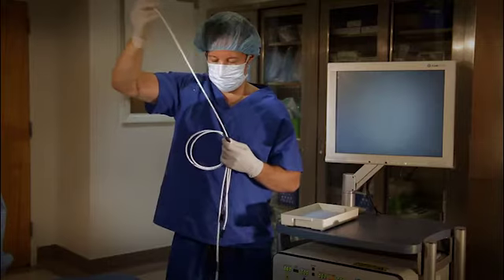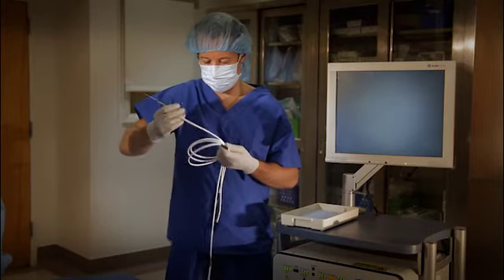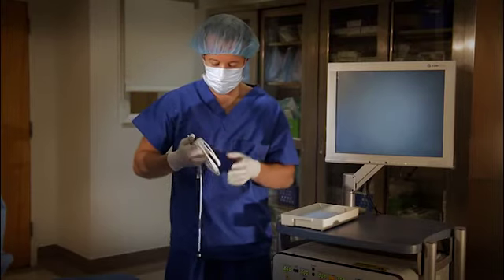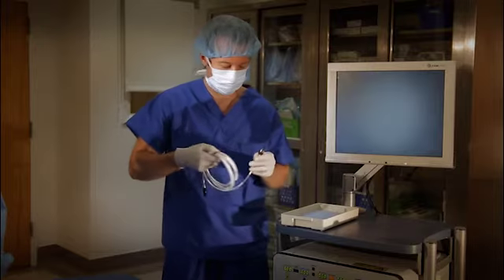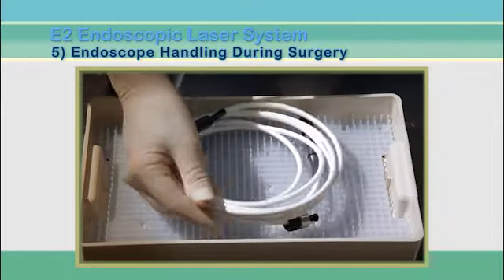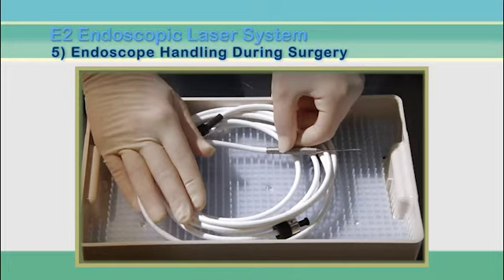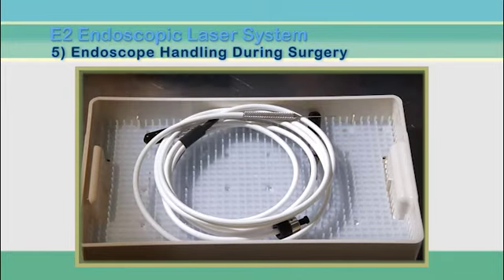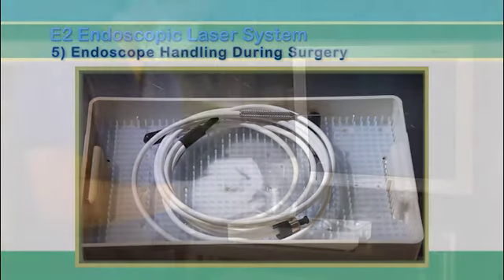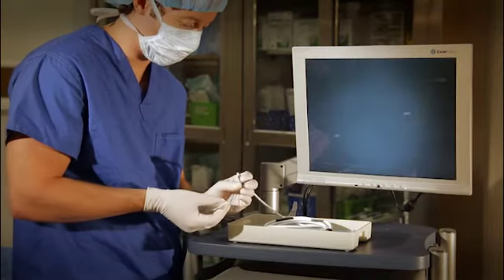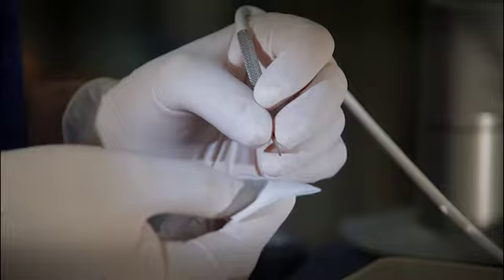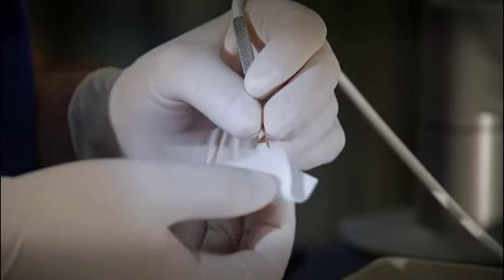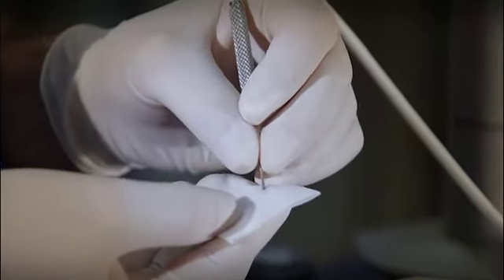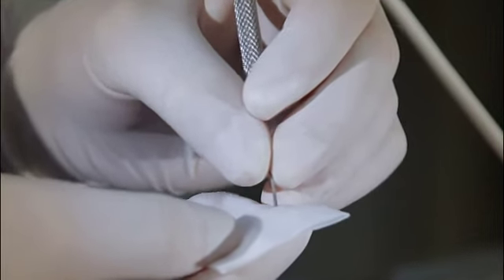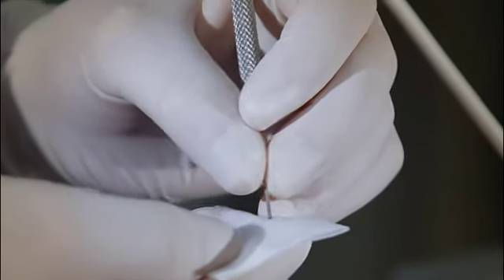Take care to pack the endoscope correctly to avoid breakage of the optical fibers. Please remember that in placing the endoscope back in the tray, it is important to coil it with the working tip at the top as shown. This will eliminate any tangles that can cause damage and will allow for convenient removal from the tray on the next use. A final cleaning of the tip is now performed, this time using an alcohol towelette. These steps are necessary to remove all viscoelastic or tissue from the tip as soon as possible after use and before re-sterilization.